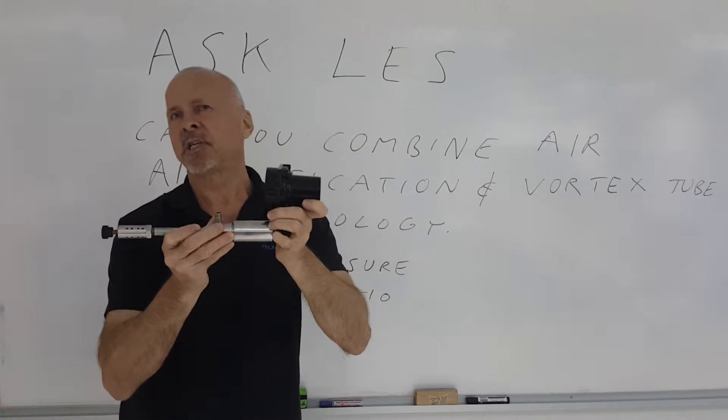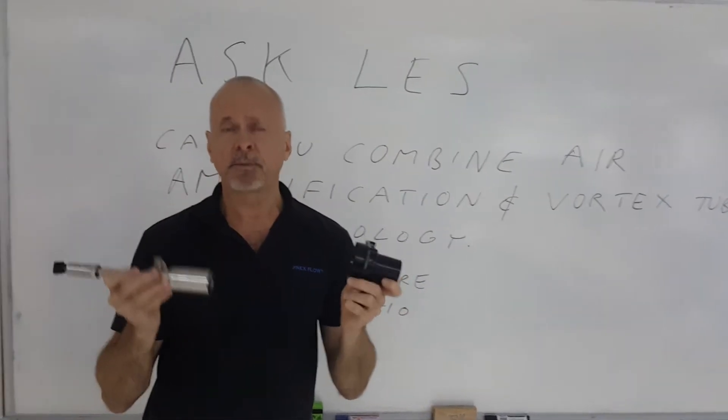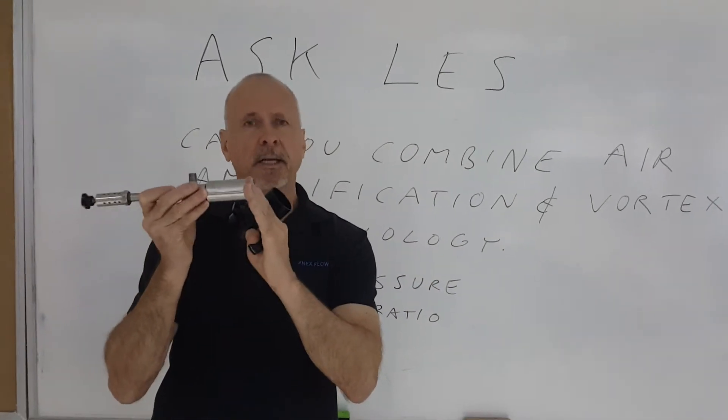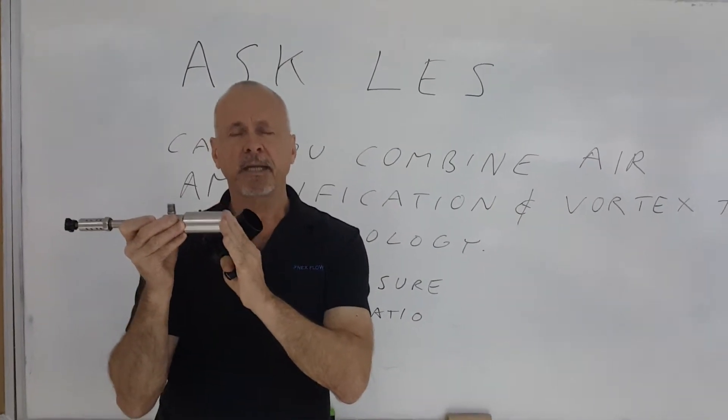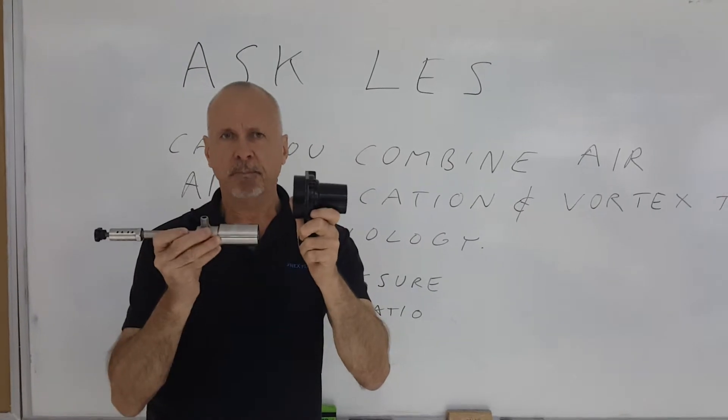Vortex tubes and amplifiers are highly subject to back pressure. For example, if I plug that end of the vortex tube, it's going to push the air back out the other side and it will simply not work. So you cannot put it in line with the amplifier.